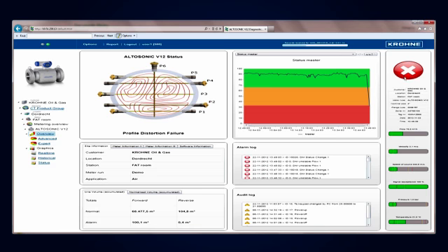Again, this is pretty logical. We blocked a large part of the meter. Okay, we go into warning, so this is very critical. It's just affecting custody transfer accuracy, just. It's borderline. There is, as you can see, a serious flow profile distortion inside the meter.